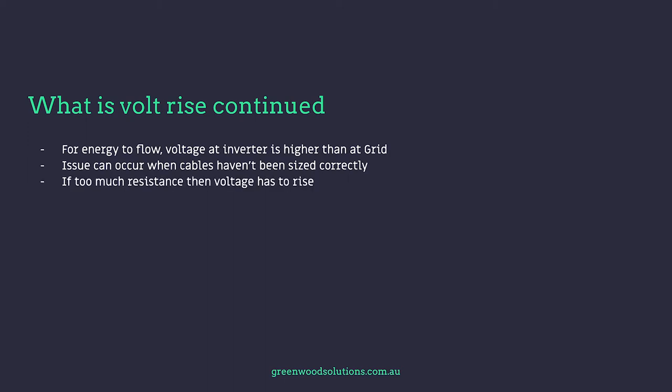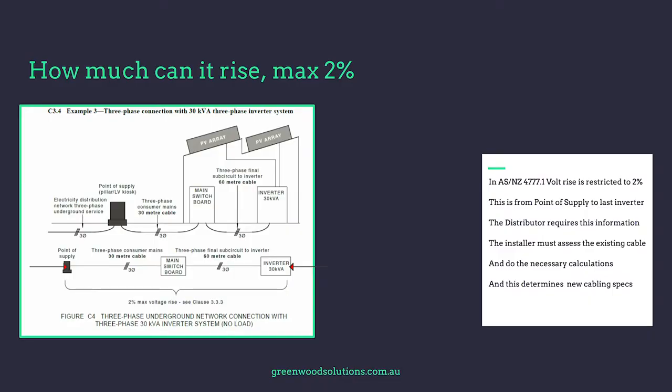If there's too much resistance in the cable, then voltage has to rise to compensate. From a volt rise perspective, it's the AC side we're talking about — not the DC side, purely the AC. In Australia and New Zealand we have standard AS4777.1, and it stipulates a maximum volt rise of two percent.